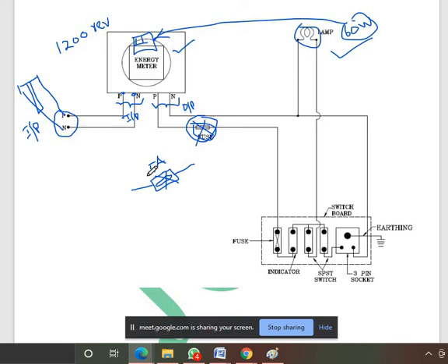You have to calculate the total load of your home, and based on the total load current, you select the fuse wire. Maybe your total load current is 6 ampere; you can fix exactly 6 ampere, but it is not required. You can go for something slightly higher, maybe 7 ampere. In the market only limited fuse wires are there: 1 ampere, 2, 4, 6, 10, 20, 25, that range.